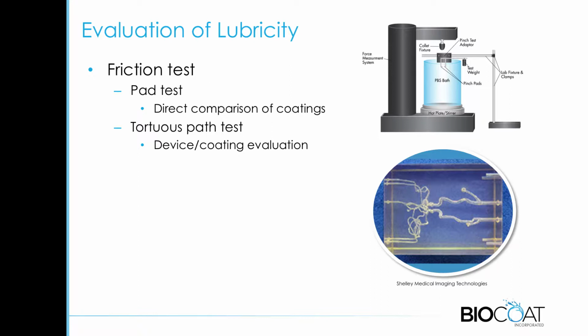For evaluation of lubricity, there are a few parts to this. There are kind of two ways of doing this. One is what I call a pad test, where you take two rubber pads, squeeze the part together, and pull it up between them under tension, usually in a hydrated solution. You're putting on an applied force, and then you're measuring the force it takes, and that should be considerably less. Best in class in a lot of these cases is at least a 10x reduction from that applied force, and even best in class is 20x. That gives a direct comparison of the different coatings and really minimizes the device design.